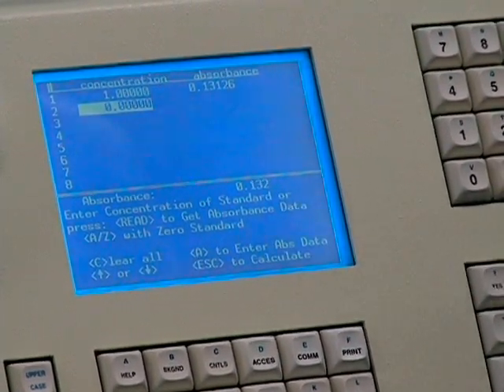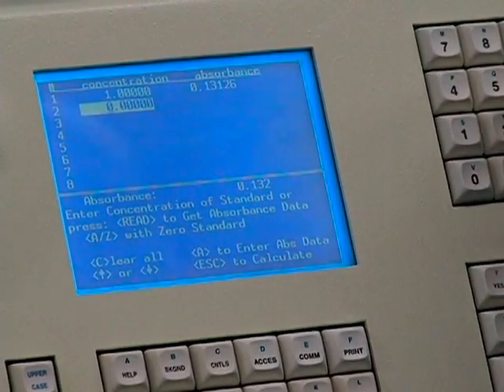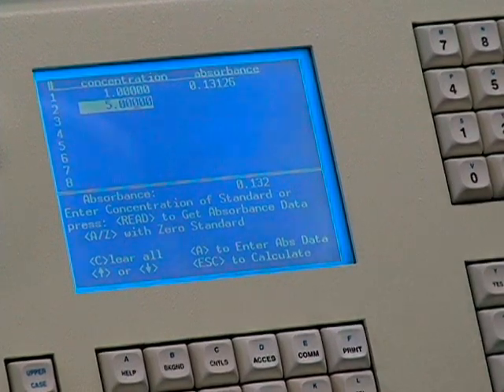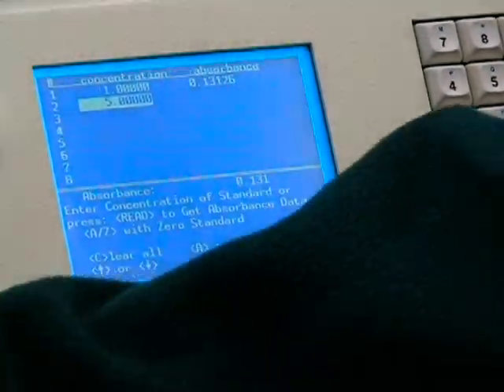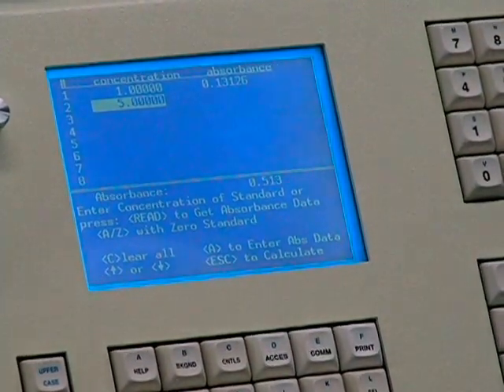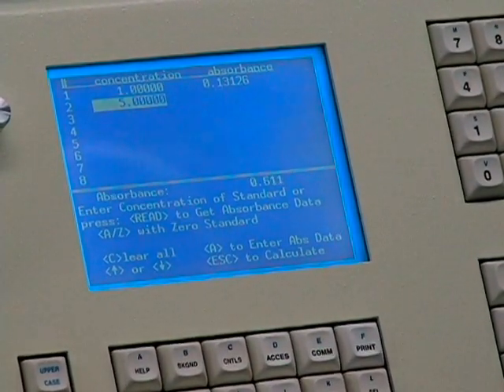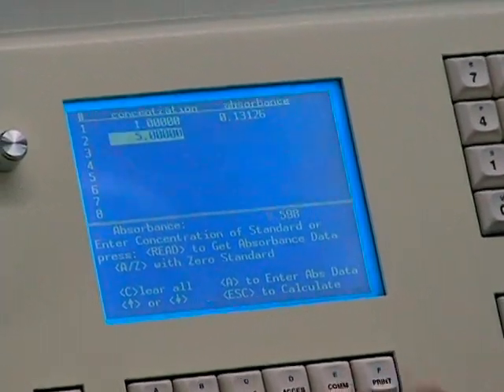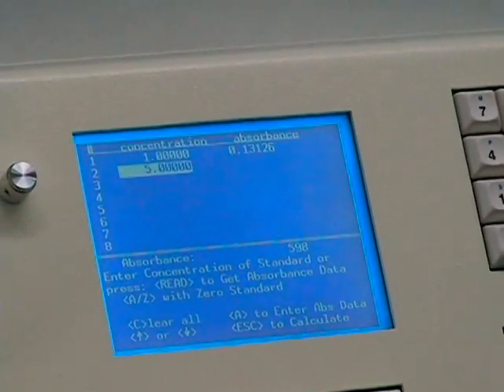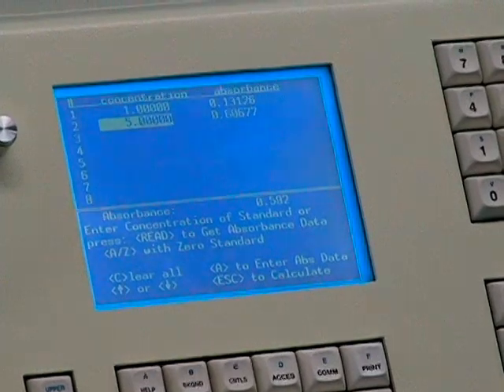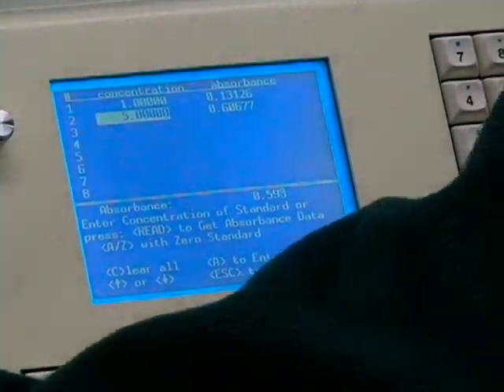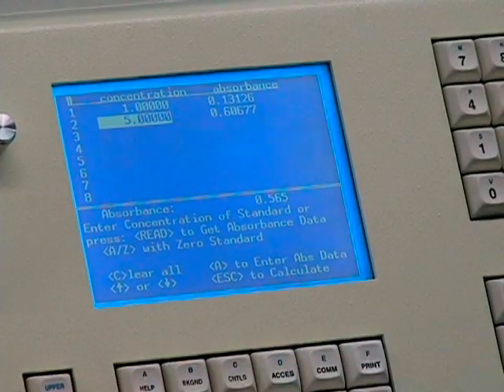Use the cursor arrows to move across to the decimal point. Enter in 5.0. Put the standard tube in the 5.0 ppm standard. Wait a few seconds and press the read key again. Once the standards have been run, go into your blank.